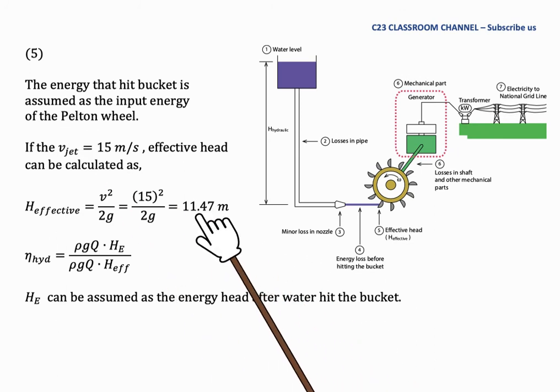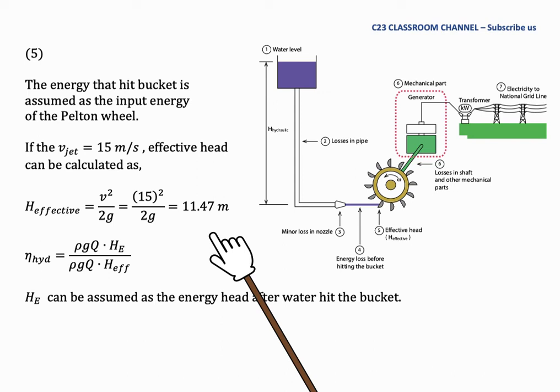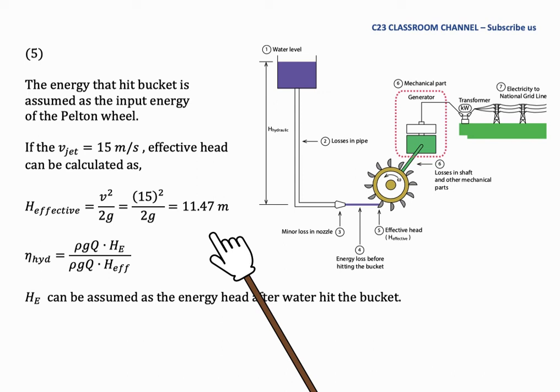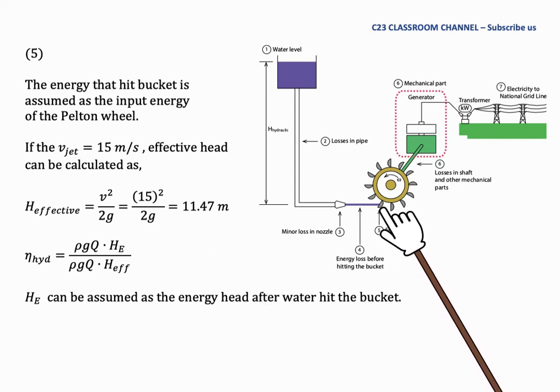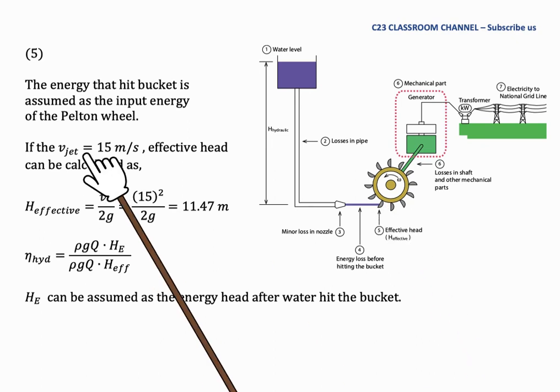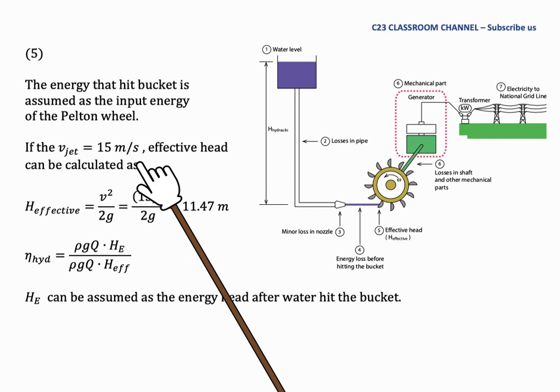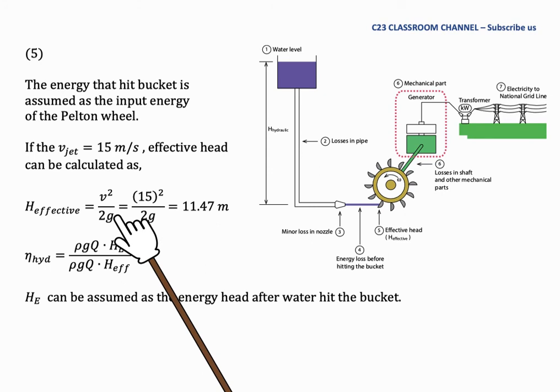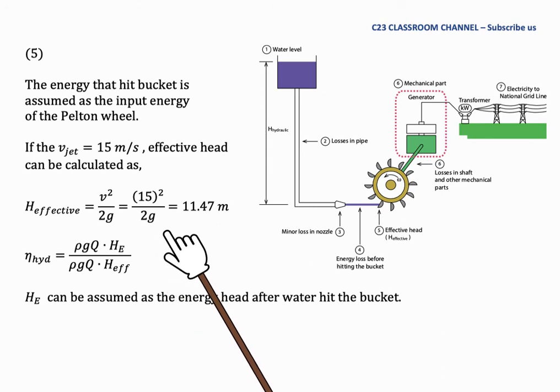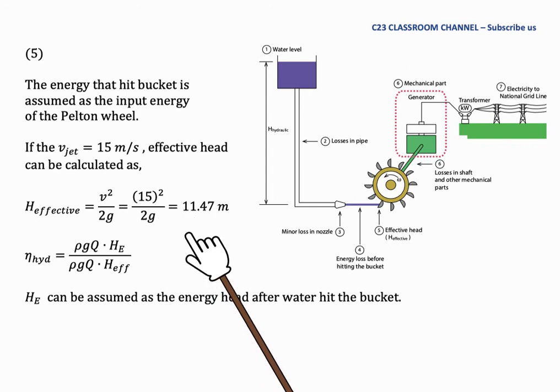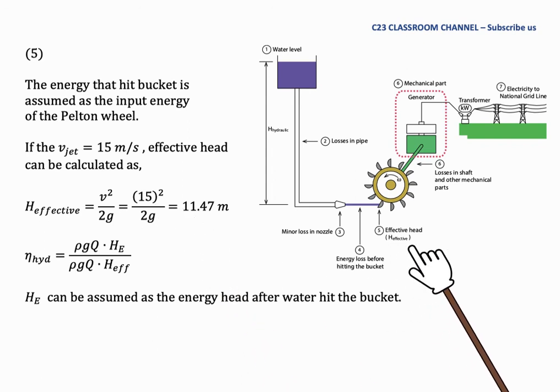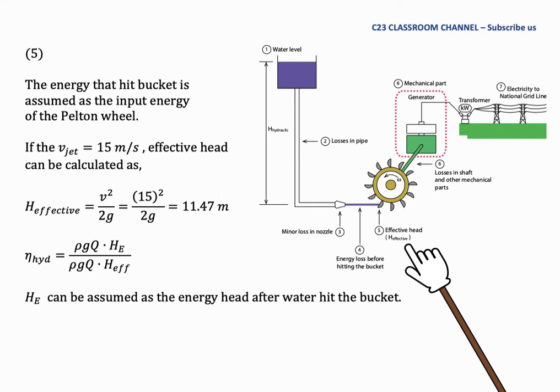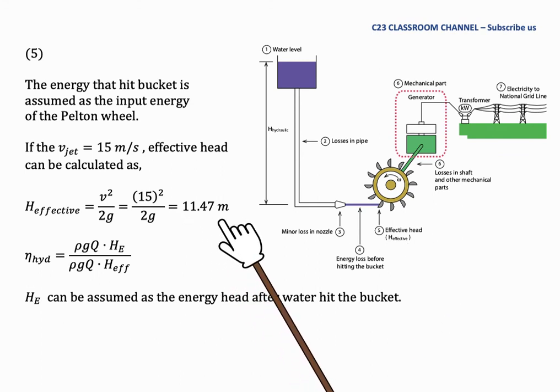The energy of the jet hitting the bucket is assumed to be the input energy of the Pelton wheel. For example, if the velocity of the jet hitting the bucket is 15 m/s, the effective head can be calculated as V²/2g. Substituting V = 15 m/s gives an effective head of 11.47 meters.